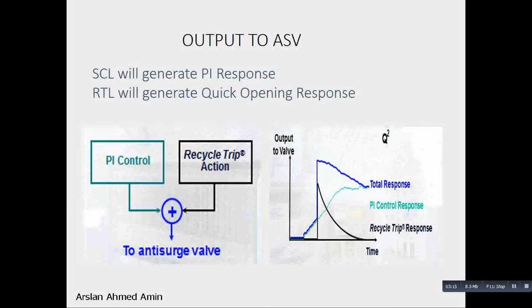So if we use a PID controller, this will cause the derivative action to act actively for closing of the valve as well. In this algorithm, the derivative action is only used to open the valve quickly. So this is the main reason, this is the main difference between a PID controller and PI plus derivative controller.